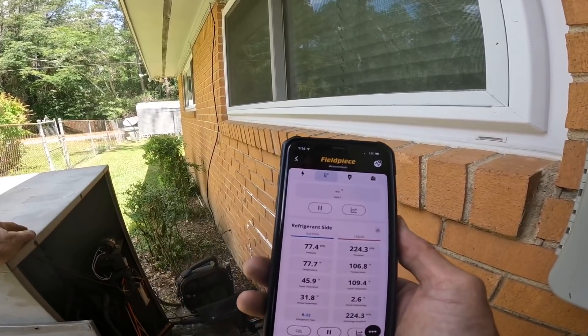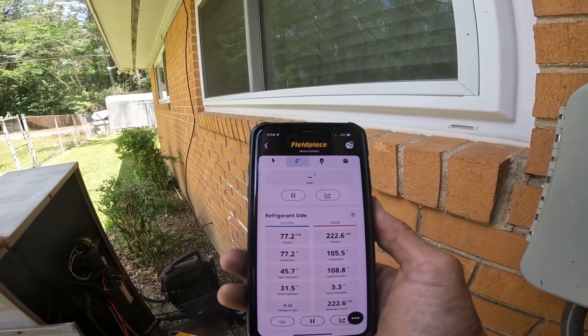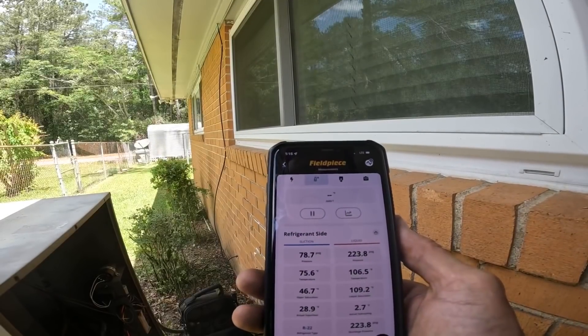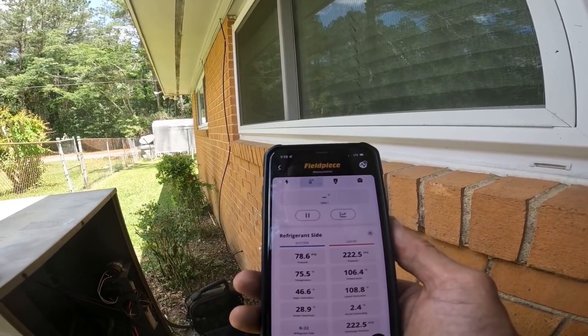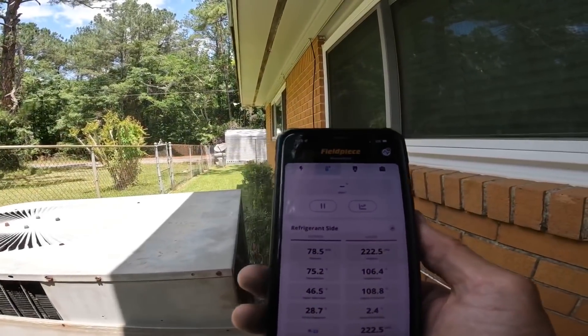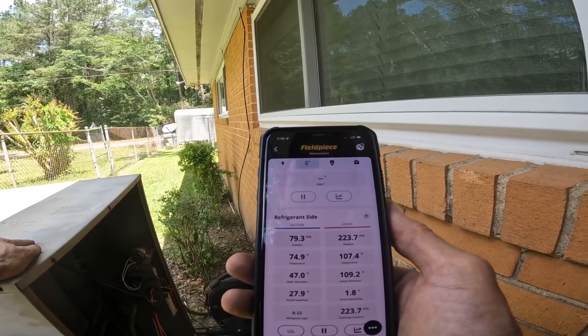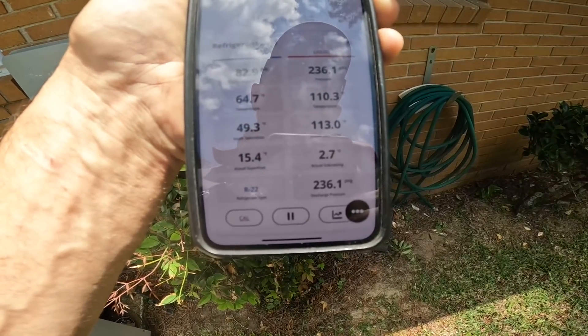I got 31 degrees superheat. There's something that's like 28 years old — this ain't too bad. We got approval to do the contactor and possibly top it off. My superheat's down to 15. This thing's going really good considering that it's a 1994 system.